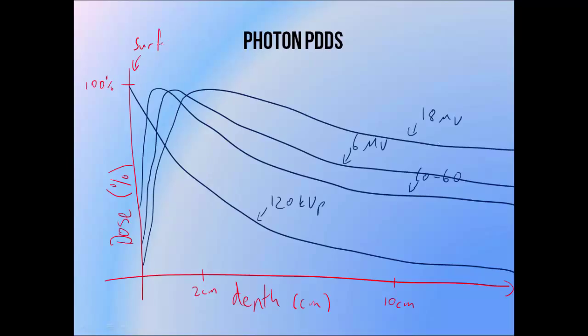The first key feature is surface dose. The kV beam deposits its maximum dose right near the skin surface, whereas a cobalt-60 beam, which is quite a low megavoltage energy beam, only deposits about 30% of its dose at the surface. 6 MV beams deposit about 15%, and 18 MV beams deposit about 10% of their dose at the surface. The majority of surface dose in these high beam energies is due to electron contamination from the treatment head.